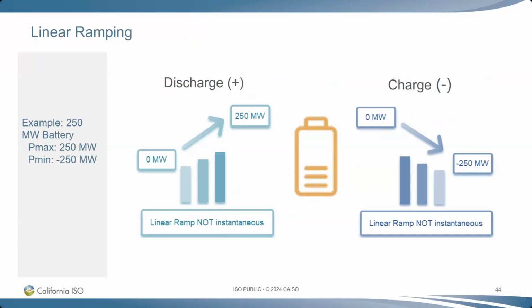From a battery standpoint, when looking at testing or ramp rates, when your resource is available, you've got the testing, but then when it's actually available, it needs to be able to be dispatched again at that 5-minute DOT. And if providing regulation, it's going to need to be able to follow a set point every 4 seconds. So ensuring the ramping capabilities of the resource during testing is key to communicating those test plans to the ISO gen dispatcher.